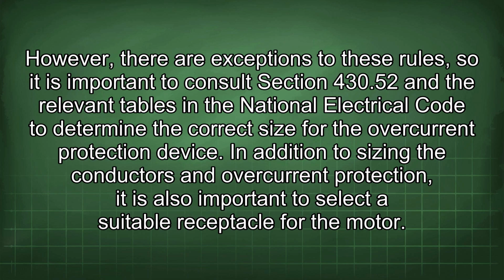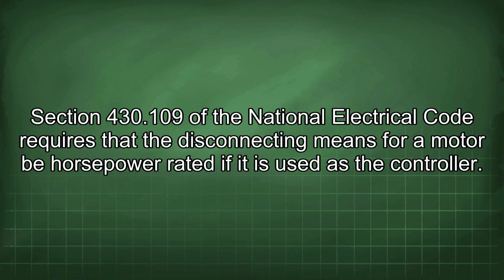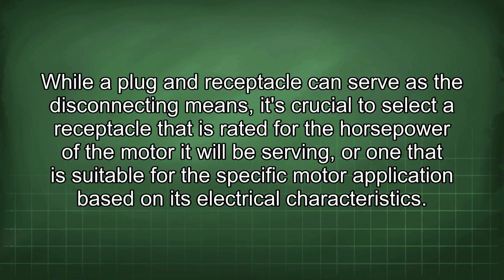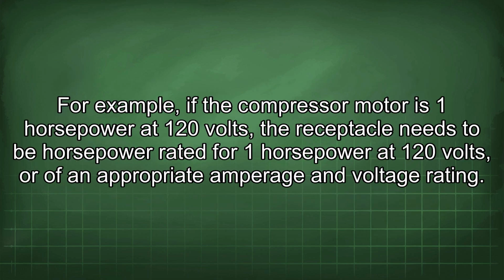In addition to sizing the conductors and overcurrent protection, it is also important to select a suitable receptacle for the motor. Section 430.109 of the National Electrical Code requires that the disconnecting means for a motor be horsepower rated if it is used as the controller. While a plug and receptacle can serve as the disconnecting means, it's crucial to select a receptacle that is rated for the horsepower of the motor it will be serving, or one that is suitable for the specific motor application based on its electrical characteristics. For example, if the compressor motor is 1 horsepower at 120 volts, the receptacle needs to be horsepower rated for 1 horsepower at 120 volts, or of an appropriate amperage and voltage rating.